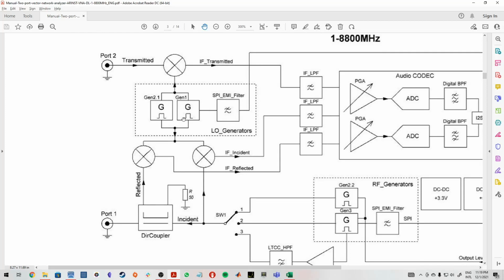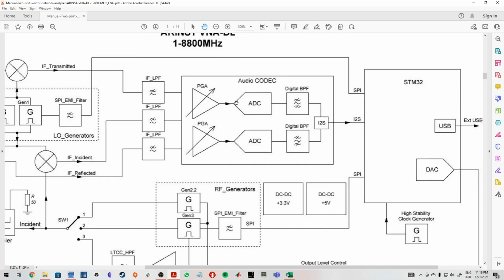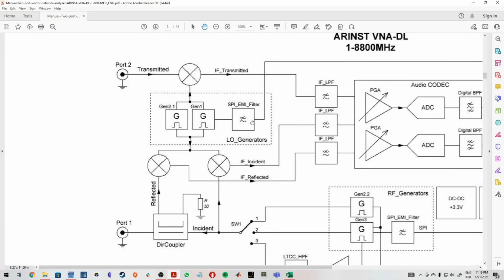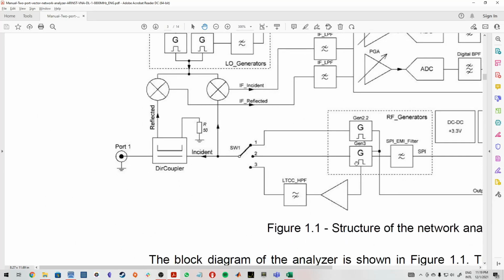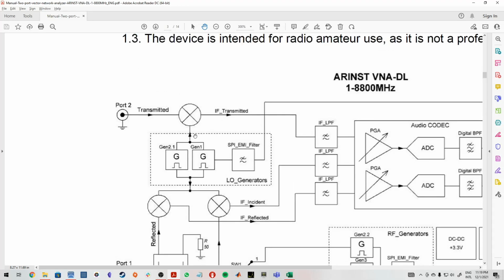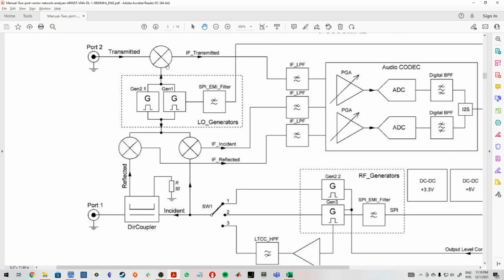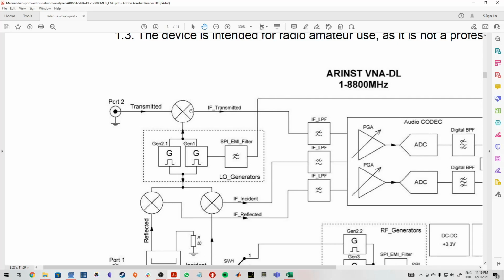But you only need two, because the harmonic will already downconvert anyway, the higher frequency, and put it on the IF signal. It's just a matter of adjusting gains and programming the IF signal here and processing later. So you actually don't need a third path in the LO, right? And then port 2 is just a mixer for the transmitted signal, and you downconvert that directly, and it's a very simple device.